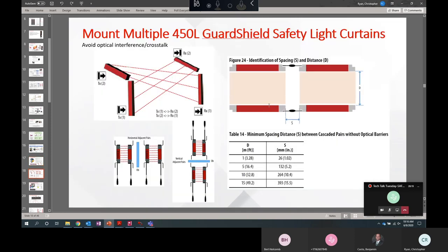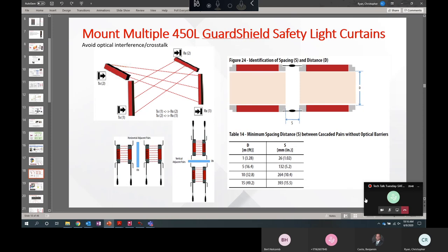I want to talk about a couple things that can happen when you mount two light curtains too closely together, whether they're cascaded or just mounted close together. You can have optical interference. That's when your receiver sporadically sees the infrared light from another transmitter. And then you've got optical crosstalk. That's when your receiver continuously communicates with the transmitter of another pair, which can cause holes in your protective field. But optical crosstalk only happens if you have the same resolution and the same height, and you don't follow the spacing guidelines here in this table. So some measures you can take to avoid that are follow the minimum spacing guidelines here in table S, depending on distance D here. You can install optical barriers, as shown in these blue bars here on the lower left picture. Or you can use beam coding, which is a feature in 450LE, which allows you to exchange the addresses of the sticks, which generates a different pulse pattern for each pair. That's referred to as beam coding.